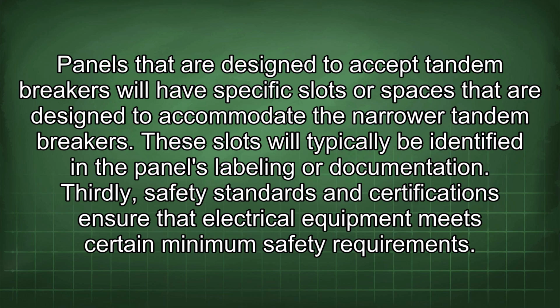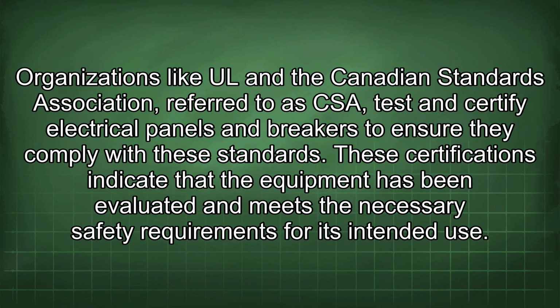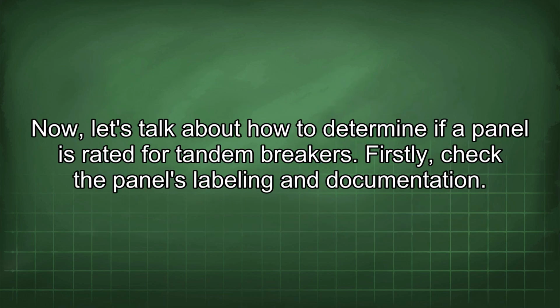Thirdly, safety standards and certifications ensure that electrical equipment meets certain minimum safety requirements. Organizations like UL and the Canadian Standards Association, referred to as CSA, test and certify electrical panels and breakers to ensure they comply with these standards. These certifications indicate that the equipment has been evaluated and meets the necessary safety requirements for its intended use. Now let's talk about how to determine if a panel is rated for tandem breakers.